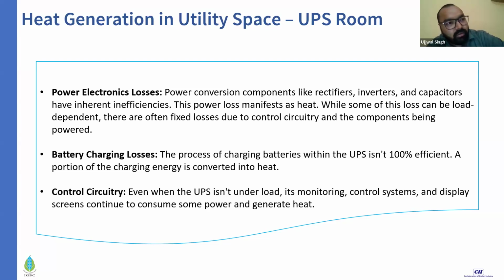Typically nowadays, with modular, hot swappable UPSs in the market, we can expect less than 3% losses from the UPS itself. In some cases, it's even gone beyond 2%.